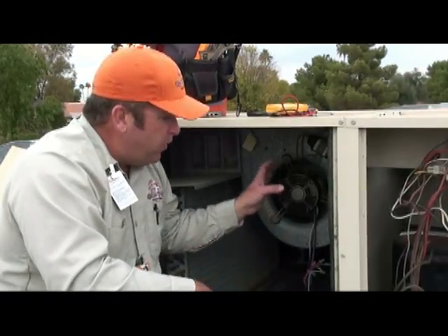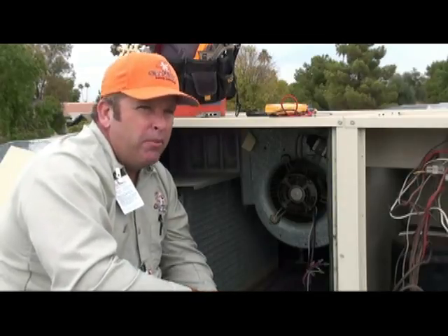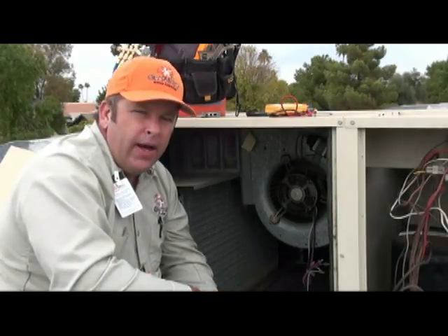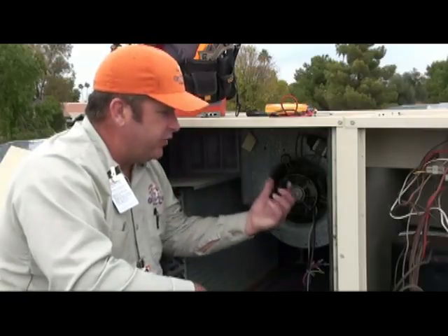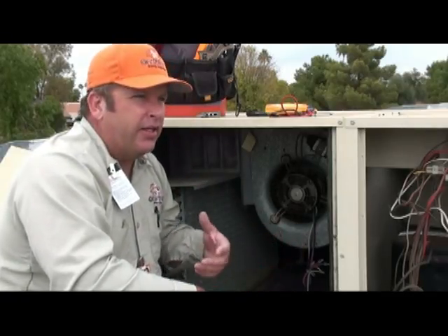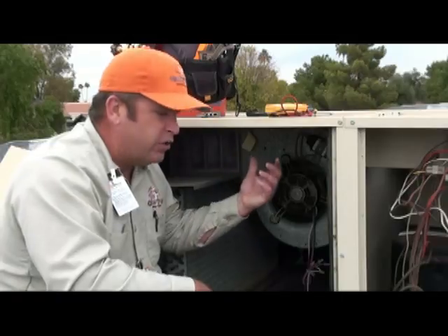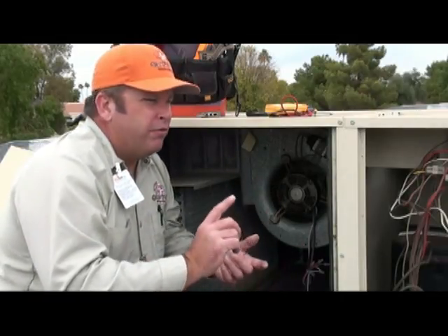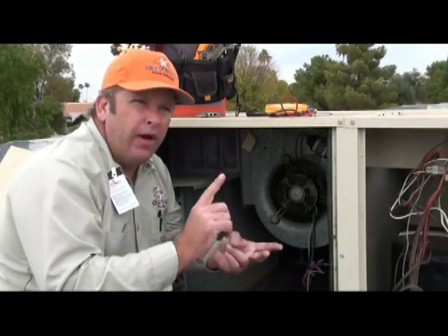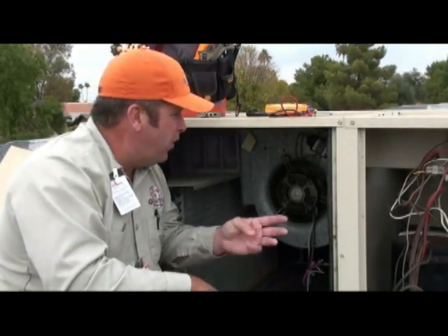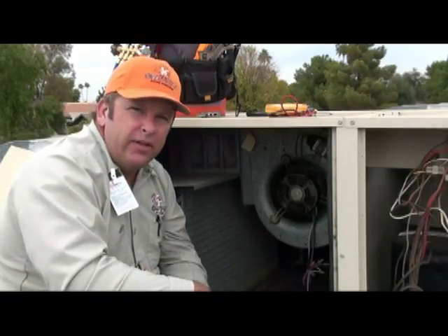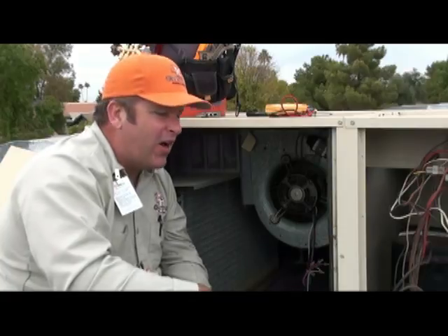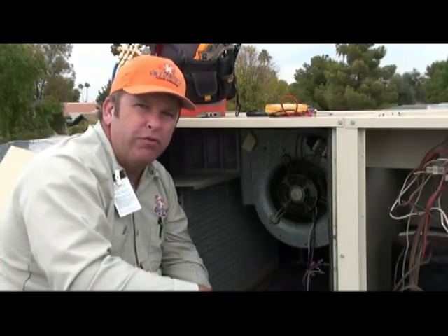Another failure mode of the motor is moisture. You want to prevent moisture from getting into these motors. Moisture will cause corrosion, which in turn can cause the bearings to go bad, can cause vibration, can cause the motor to be loud. All of those are symptoms of dirt getting into the motor, of moisture getting into the motor, of the motor just not being cleaned in general. Those are all preventable things, and those are all things that commonly cause the motor itself to fail.